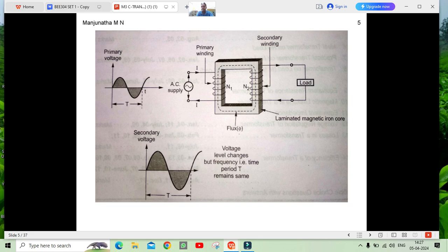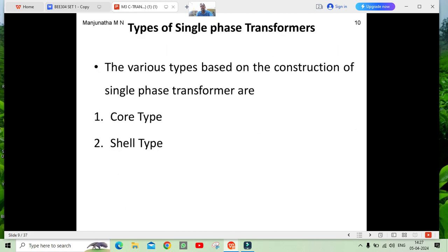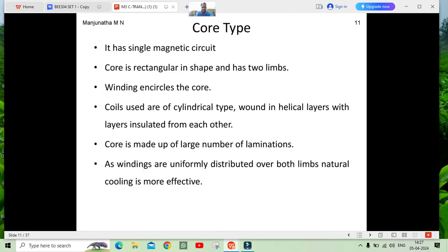Coming to the types of transformer: we have generally core type and shell type. For the core type, it has a single magnetic circuit and the core is rectangular in shape. In this case, most of the winding encircles the core.